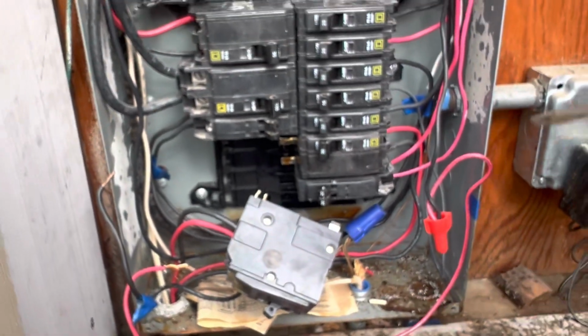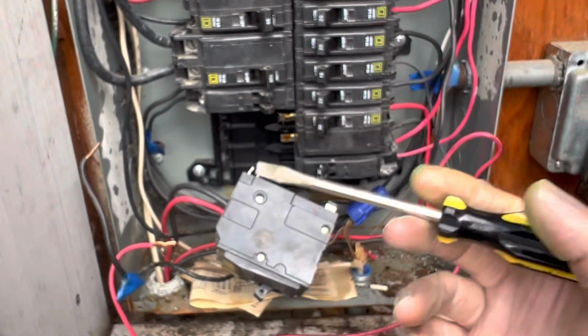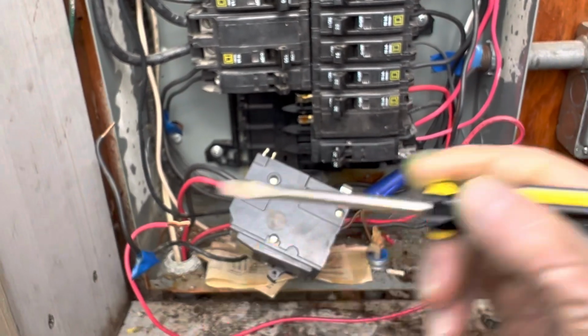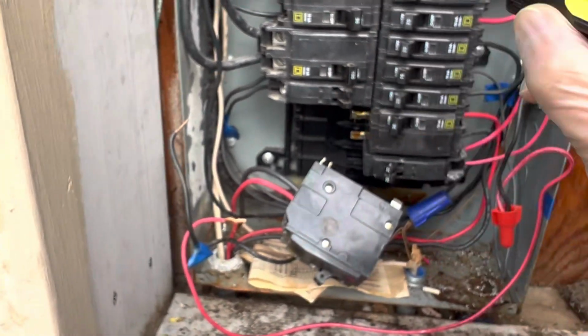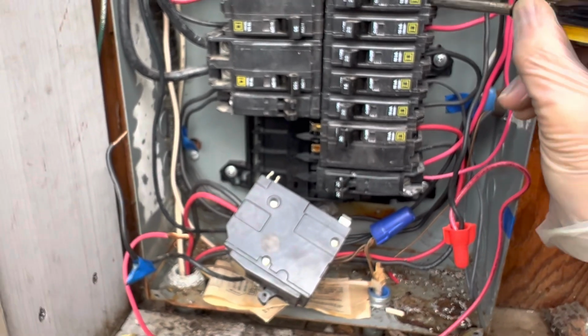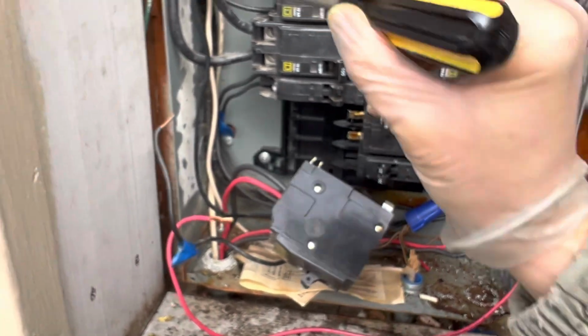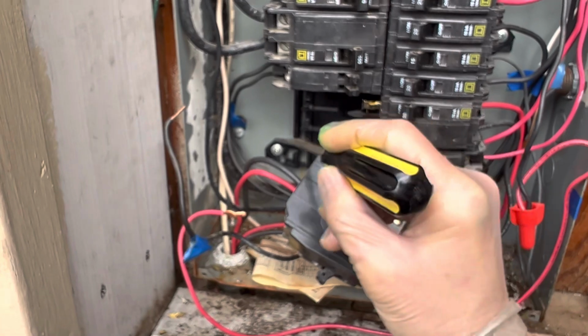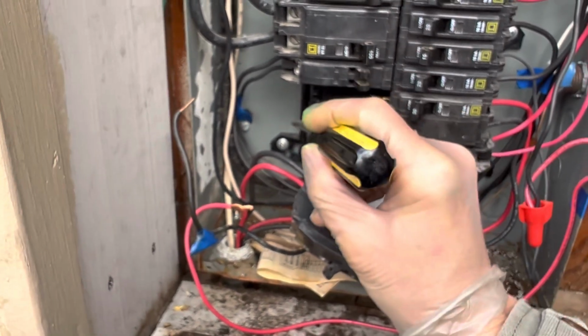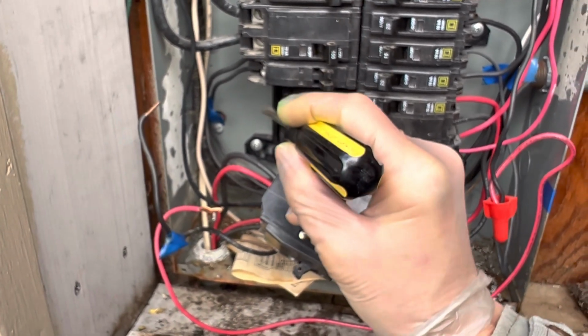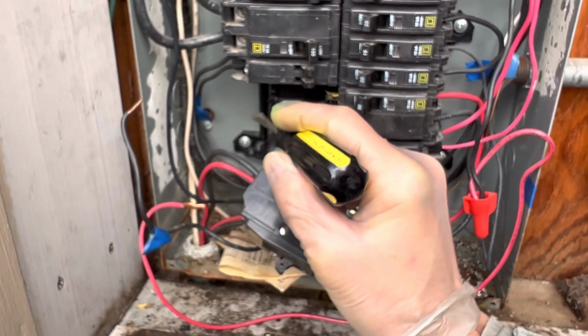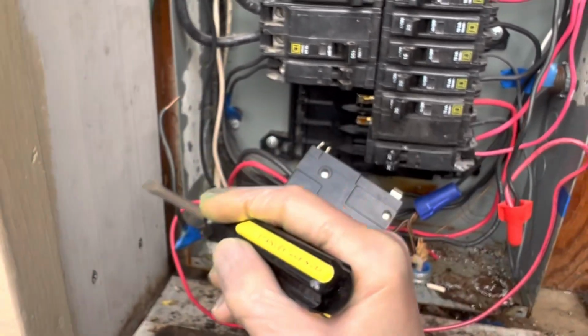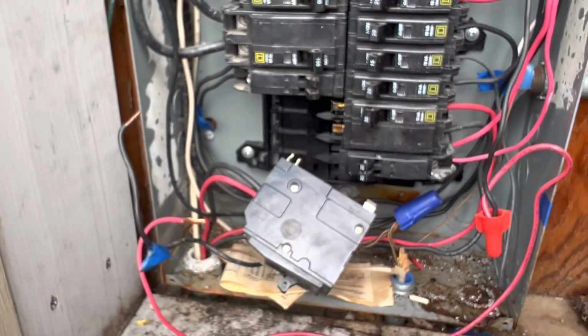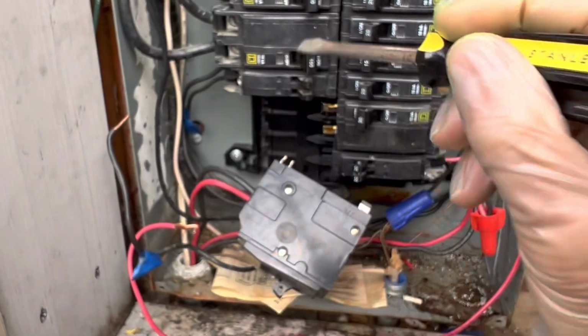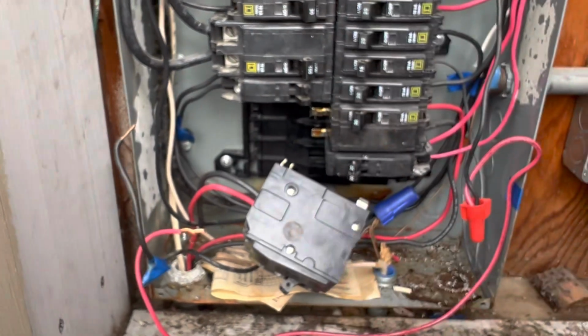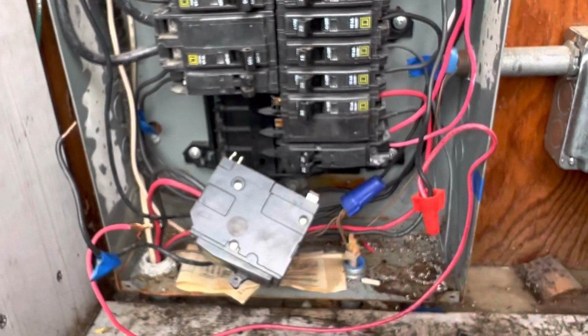Oh, and by the way, getting back to how I found it -- I didn't have my amp clamp with me. My son was here and he just had a voltmeter, so I did a voltage drop test. Like I said before, everyone was 125 until I came across one that was 123. And I thought, okay, this 123 has to be that cooker, because the cooker draws about 10, 12 amps. So I flicked off that circuit breaker, and sure enough, it was that cooker. So instead of using an amp clamp, that was my method to find that circuit voltage drop, because it was a high amperage draw.